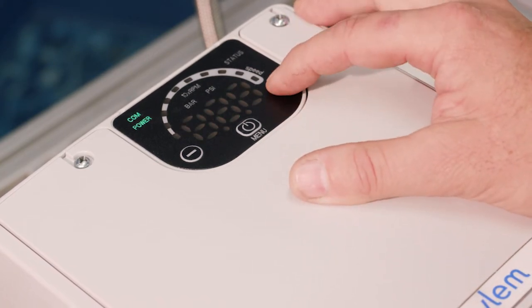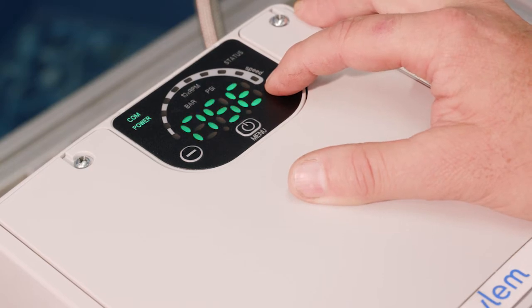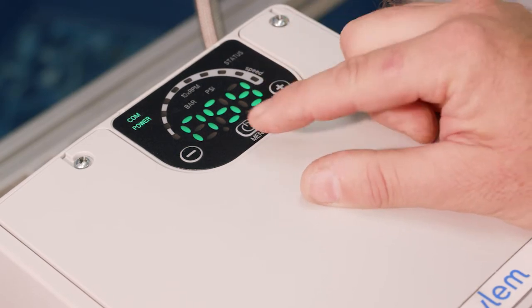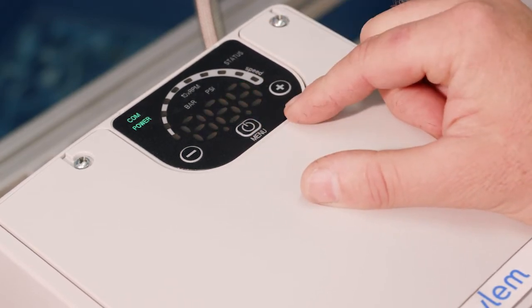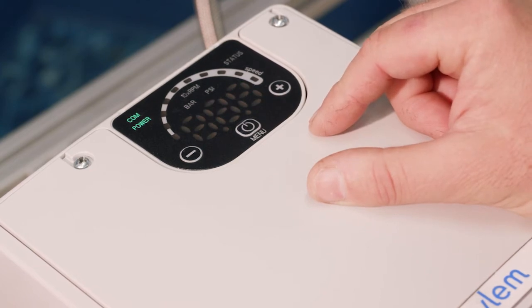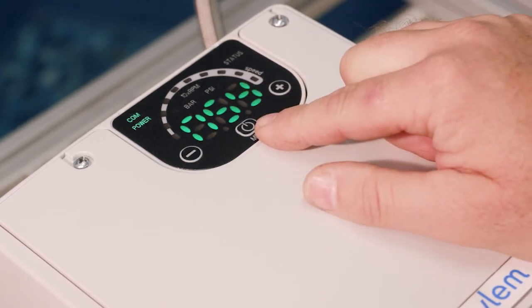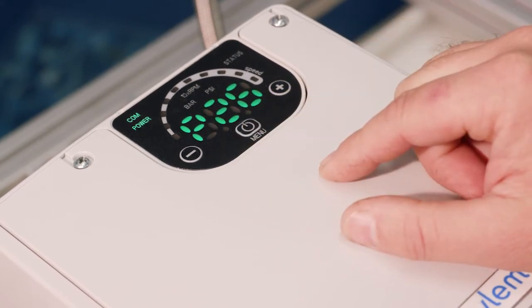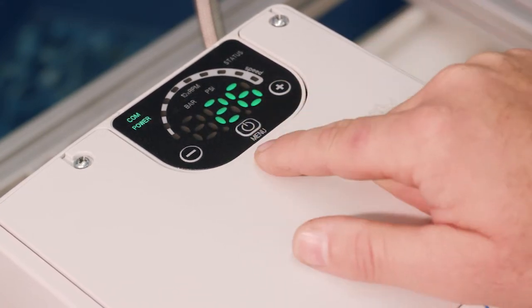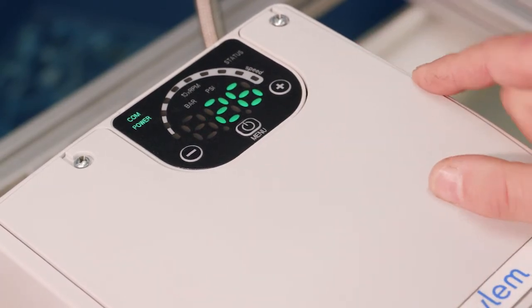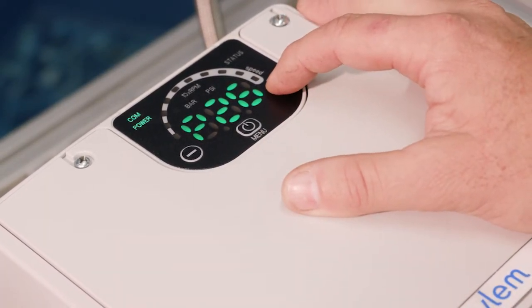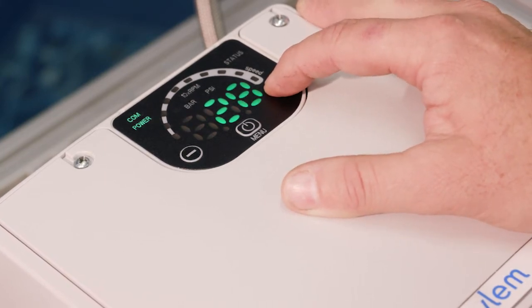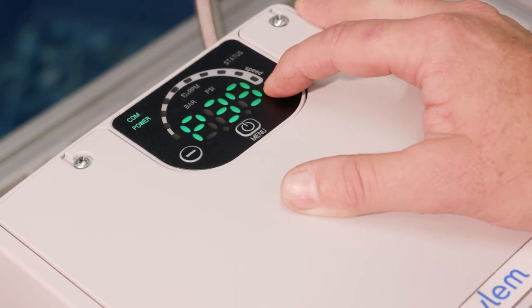So what you have to do is decide, again, we got a duplex, so we have 2 options. We have multi-pump Cascade serial or multi-pump synchronous. Let's just look at synchronous in the beginning. Okay, so I'm going to set this to synchronous. Now again, I'm going to do the same exact thing on drive 2. So what is the next parameter that we have to hit as a minimum to set this up? And that's going to be 55. So let's go all the way to 55.